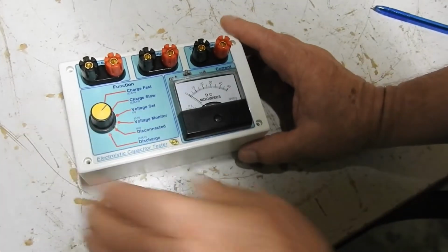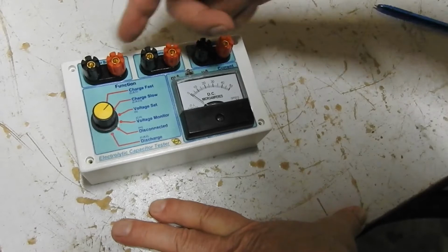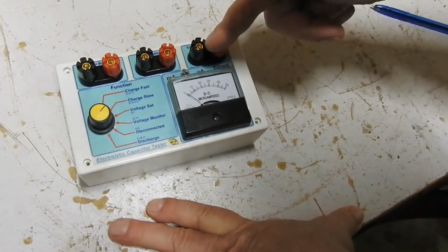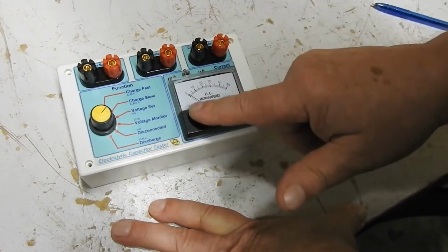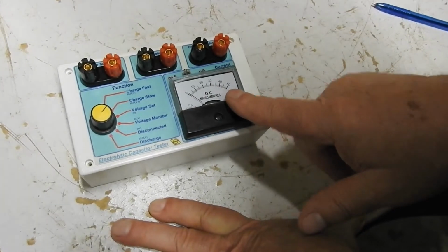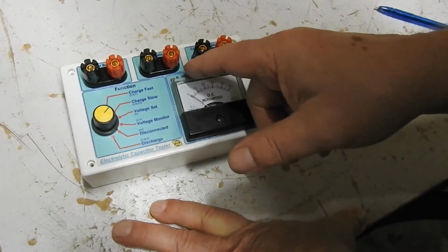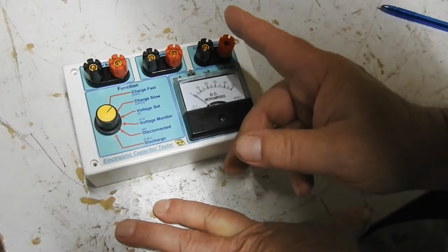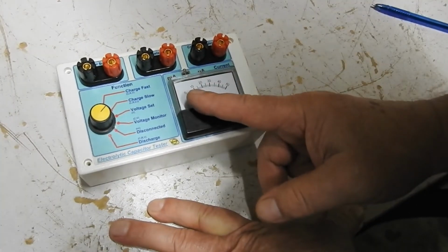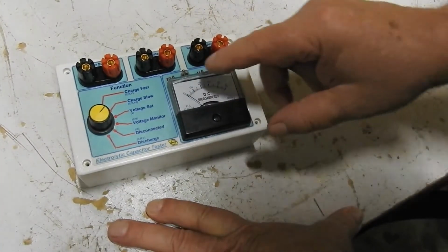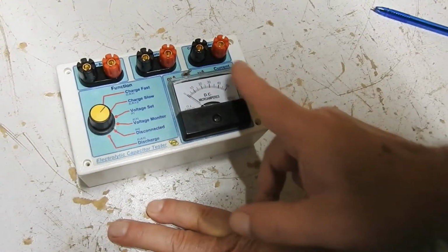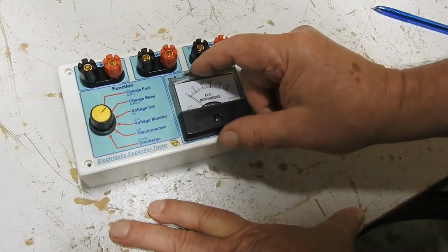Then switch it to charge slow, so it starts putting the power supply into the capacitor, and you can monitor the current on the meter in the milliamp range. It'll eventually drop down until it gets to a very low current, hopefully, if there's nothing wrong with the capacitor, and then you can switch to microamps and see it drop down further with more accuracy.